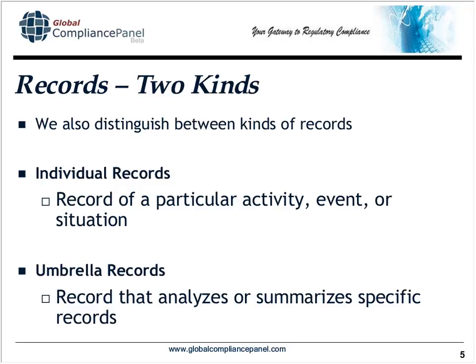We're going to look at two kinds of records. Individual records are created when you perform a particular activity — an event or situation causes you to create a standalone record. But sometimes we also have to analyze and summarize specific records. Data analysis in ISO 13485 and FDA regulation 820.100(a)(1) requires us to analyze data. That data analysis is going to create what I'll call an umbrella record — a record that covers multiple individual records and summarizes information from those records.